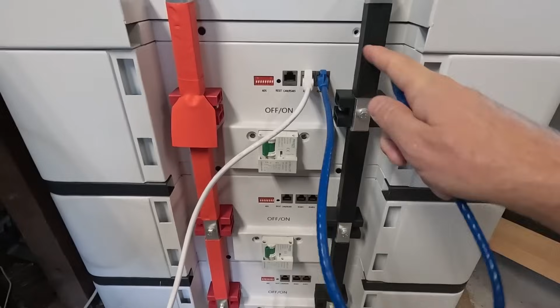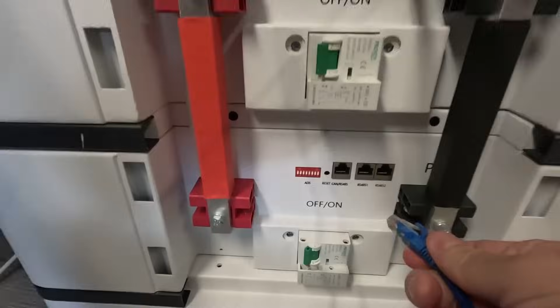So we go from RS485 number 2 to RS485 number 1 on the next battery. And then we use another patch cable, go from RS485 number 2 again down to port number 1 for battery number 3. So now we've got them all communicating with each other automatically. This is the only way you can do it if you have all your dip switches set on 0.